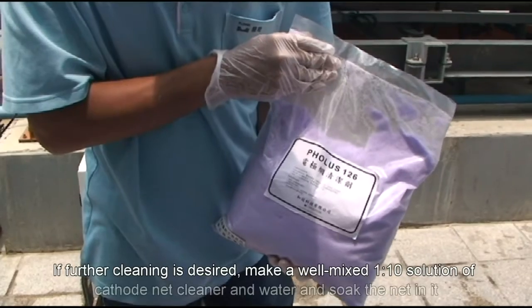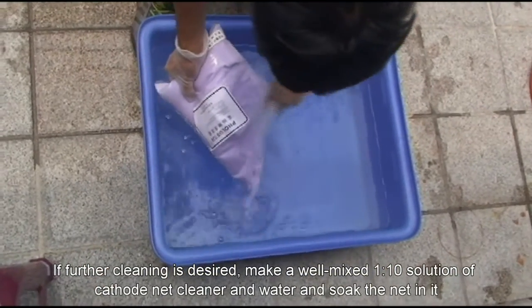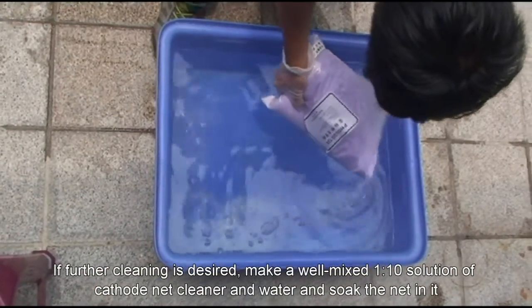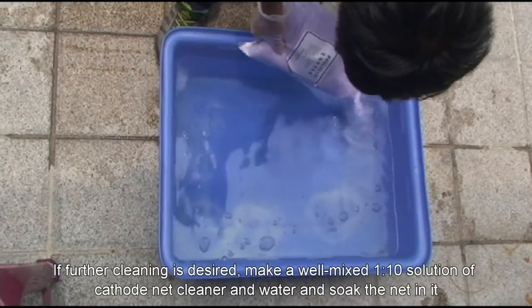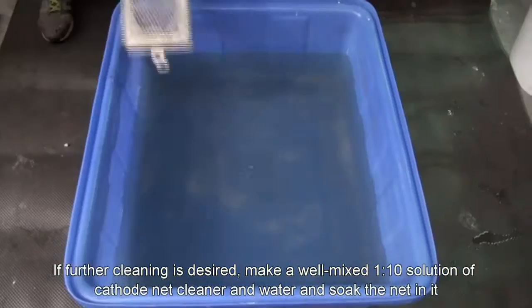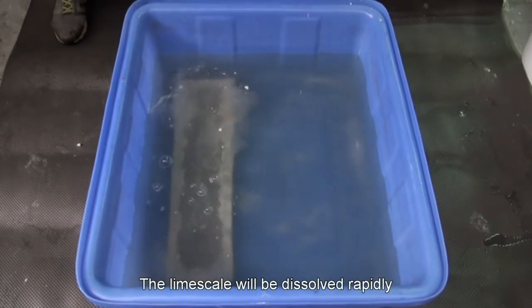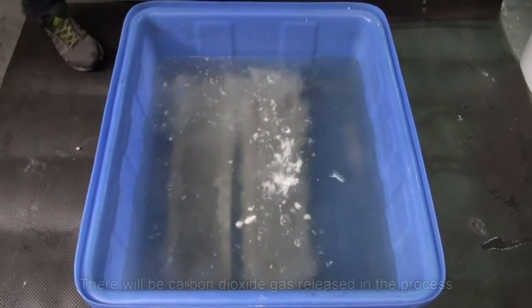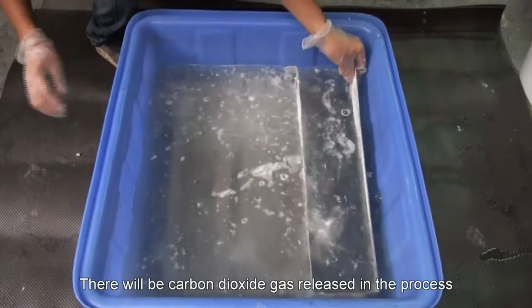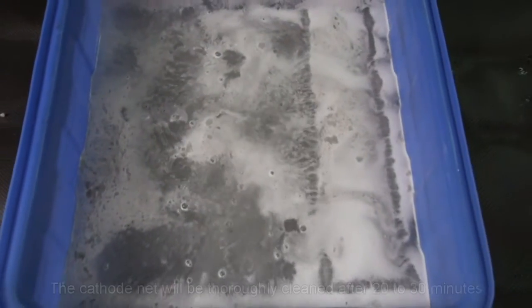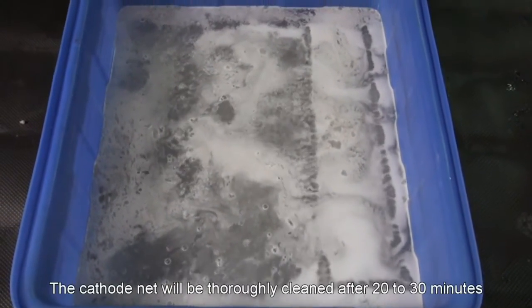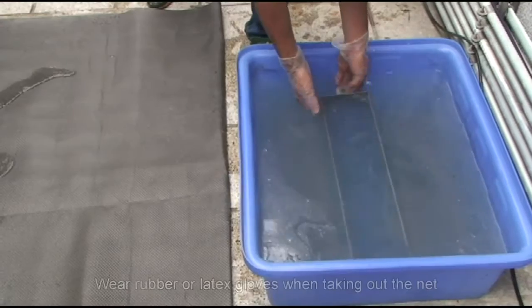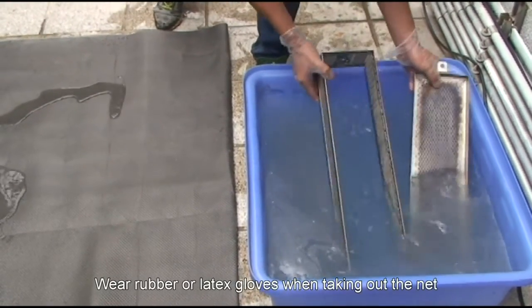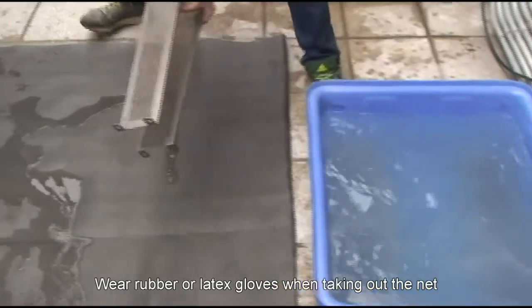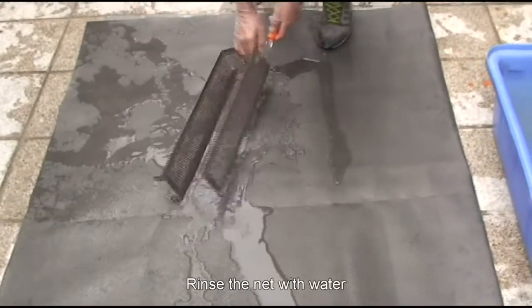If further cleaning is desired, make a well-mixed 1 to 10 solution of cathode net cleaner and water and soak the net in it. The limescale will be dissolved rapidly. There will be carbon dioxide gas released in the process. The cathode net will be thoroughly cleaned after 20 to 30 minutes. Wear rubber or latex gloves when taking out the net. Rinse the net with water.